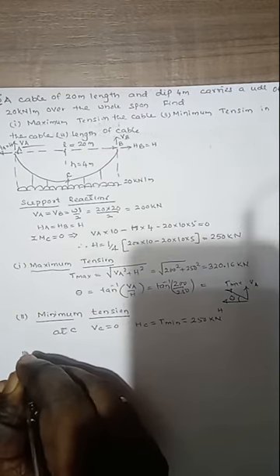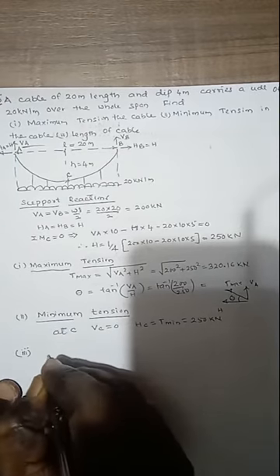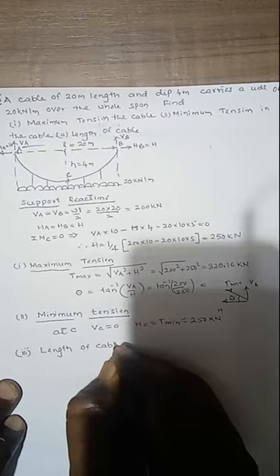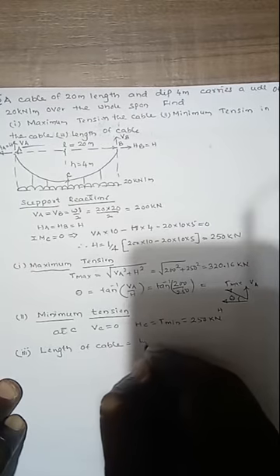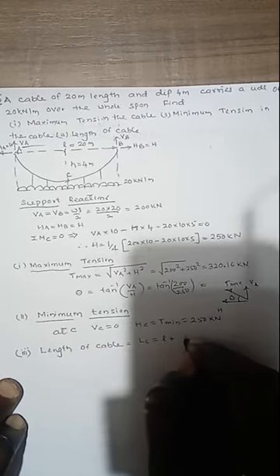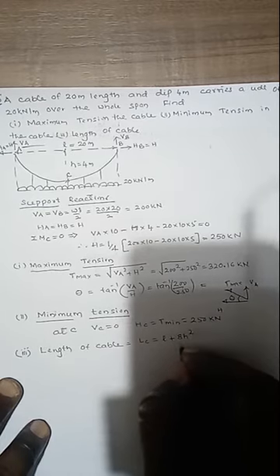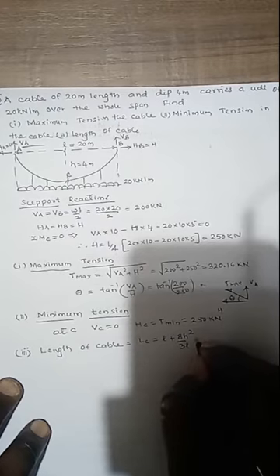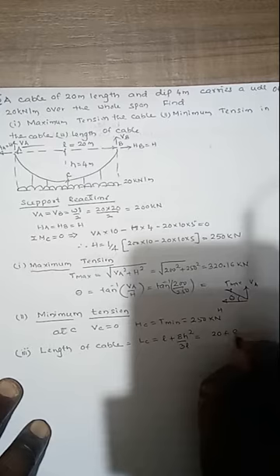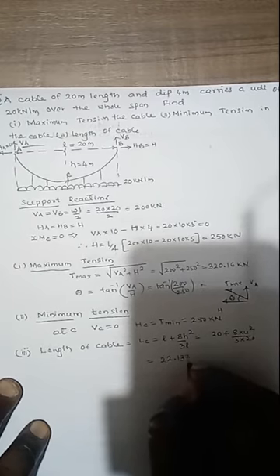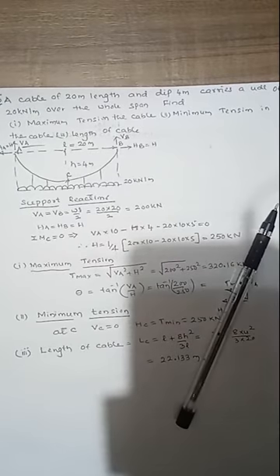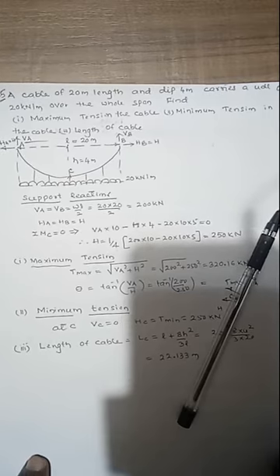The length of the cable is given by: L_cable = L + (8 × H²)/(3L) = 20 + (8 × 4²)/(3 × 20) = 22.133 m. This is the solution for Problem 2.